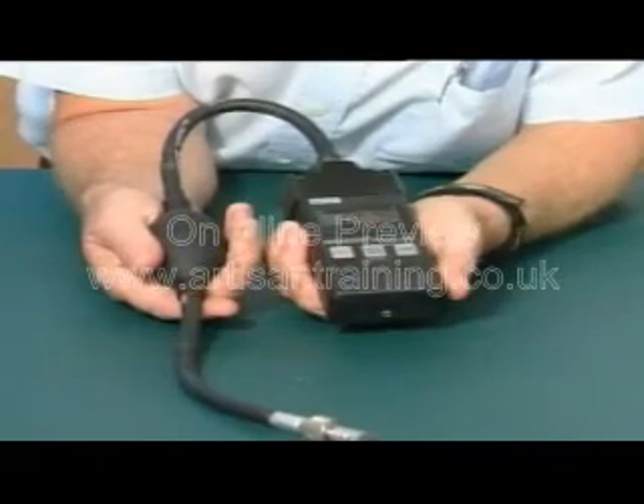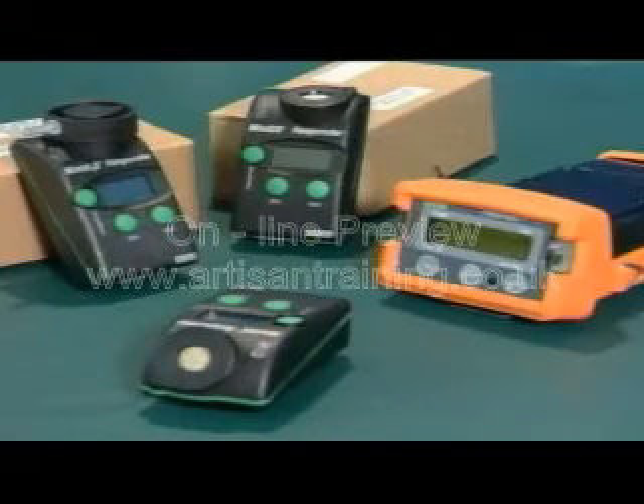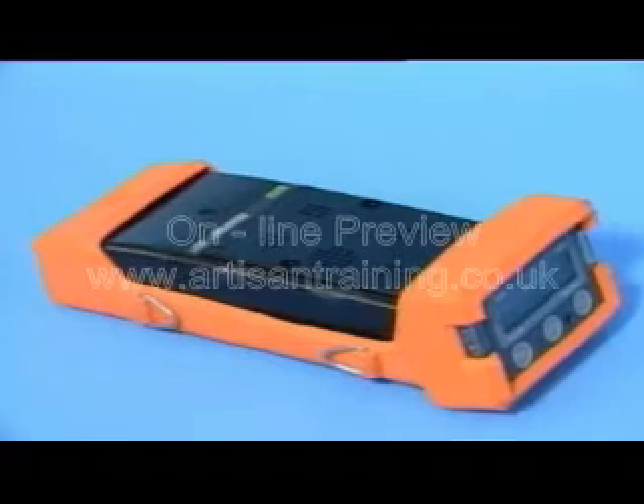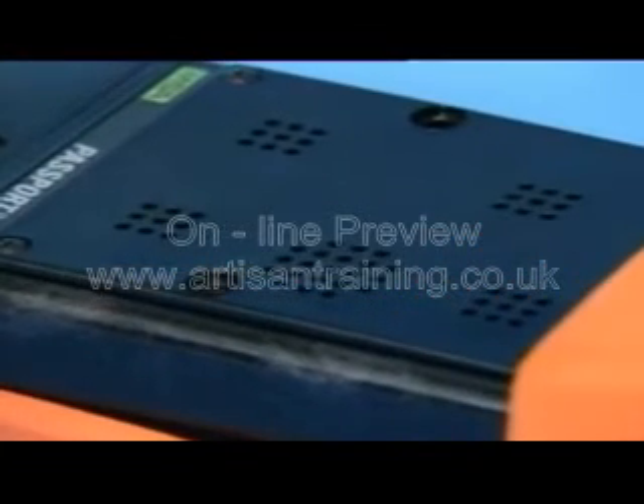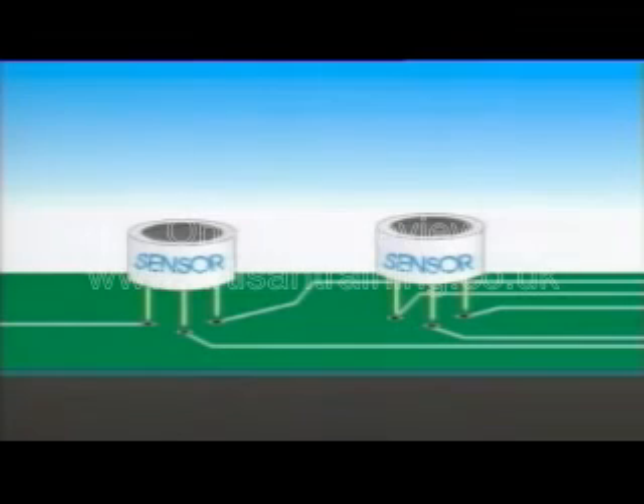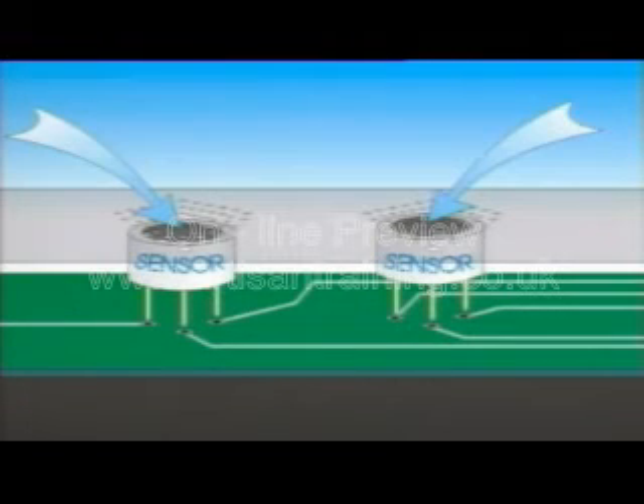There are various types of monitoring devices, and we shall be concentrating on typical models currently in popular use within industries all over the world. First, we need to explain a little about how monitors or gas detectors operate. In principle, they all draw air into sensors through a diffusion plate. Sensors are made in various types, but in effect they react chemically to airborne substances and then send electrical signals to the electronic circuits within the instrument.